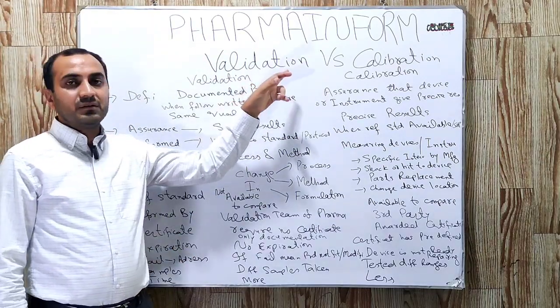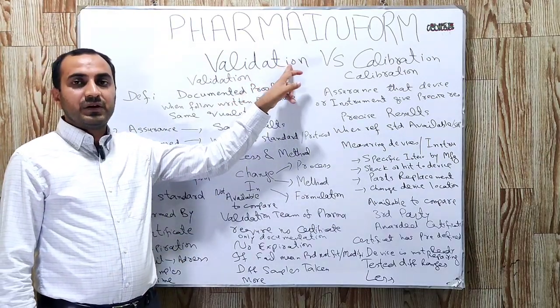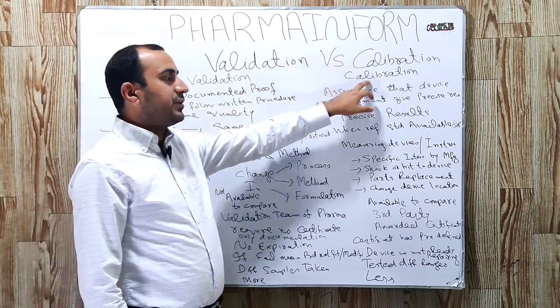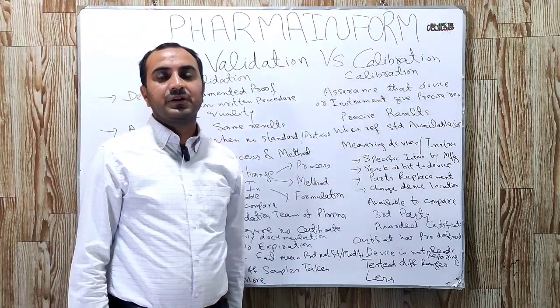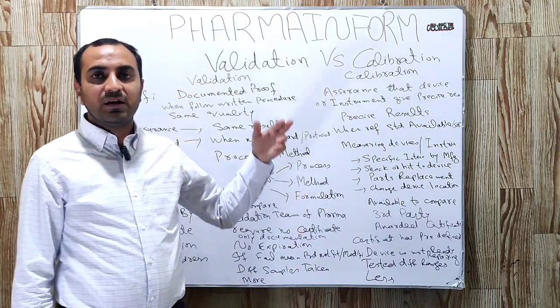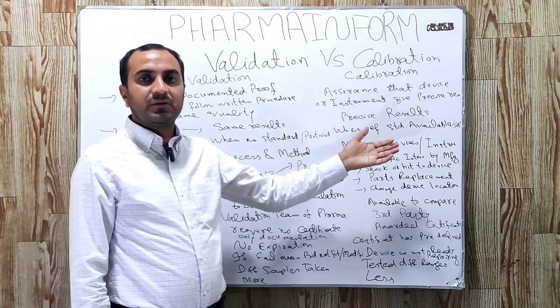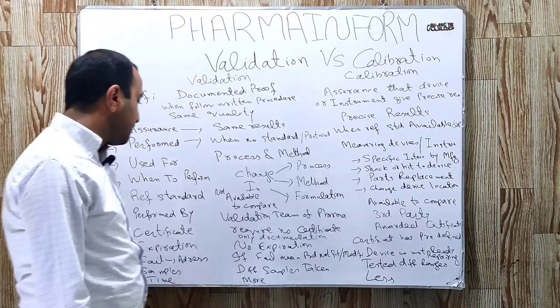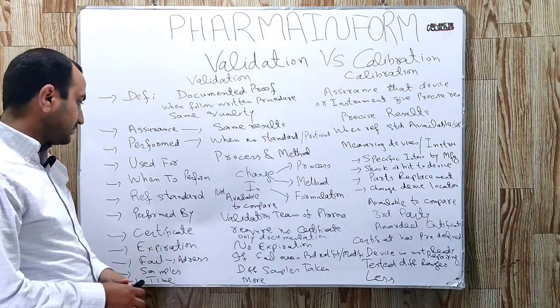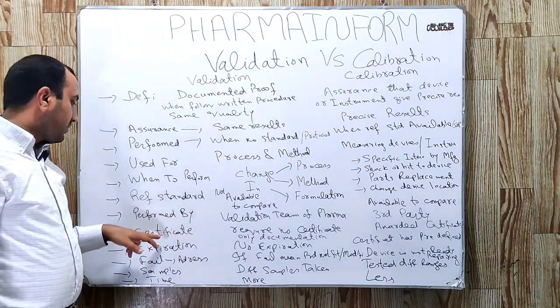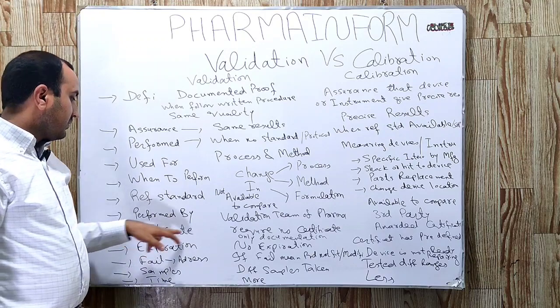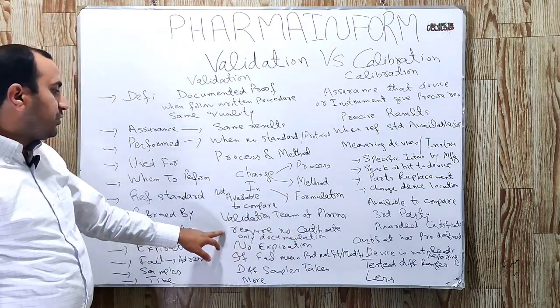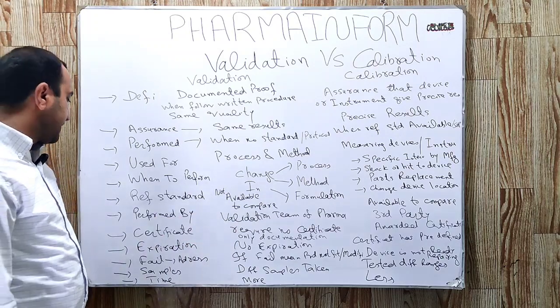Regarding certification: validation requires no certificate; we only use documentation. For calibration, after the activity is completed, a specific certificate of calibration is issued for that instrument or device.